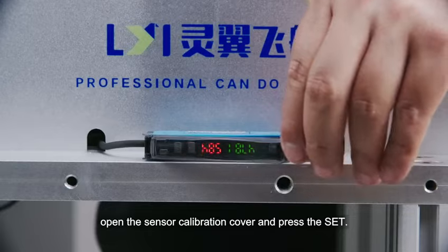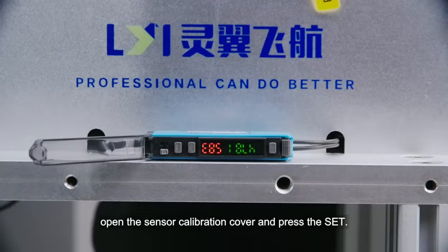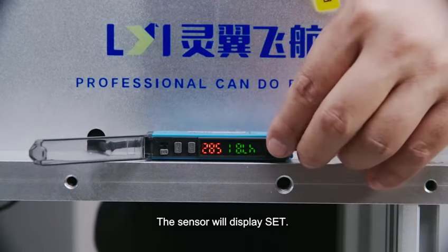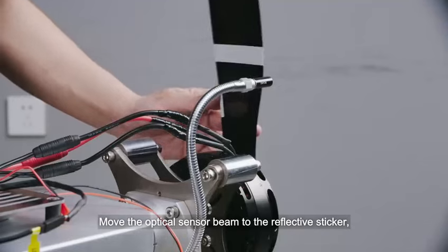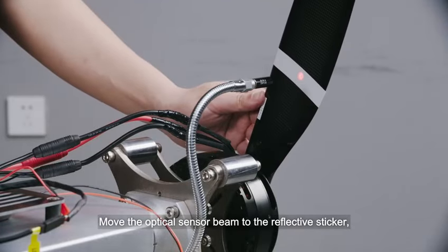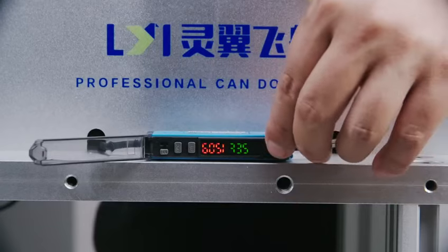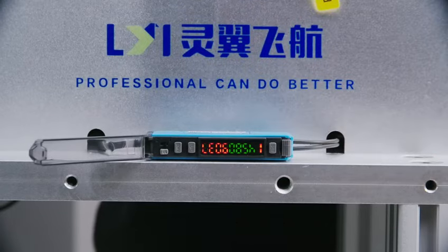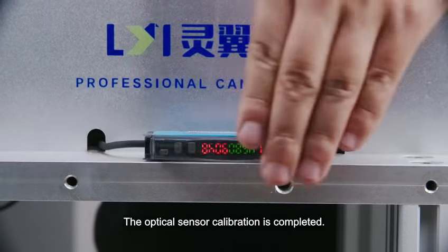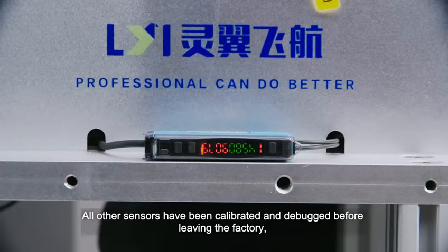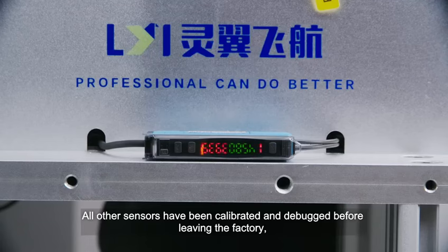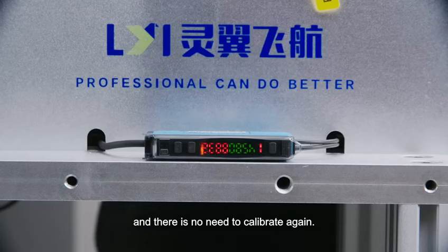Open the sensor calibration cover and press the set. The sensor will display set. Move the optical sensor beam to the reflective sticker on the propeller. Press the set button again. The optical sensor calibration is completed. All other sensors have been calibrated and debugged before leaving the factory, and there is no need to calibrate again.